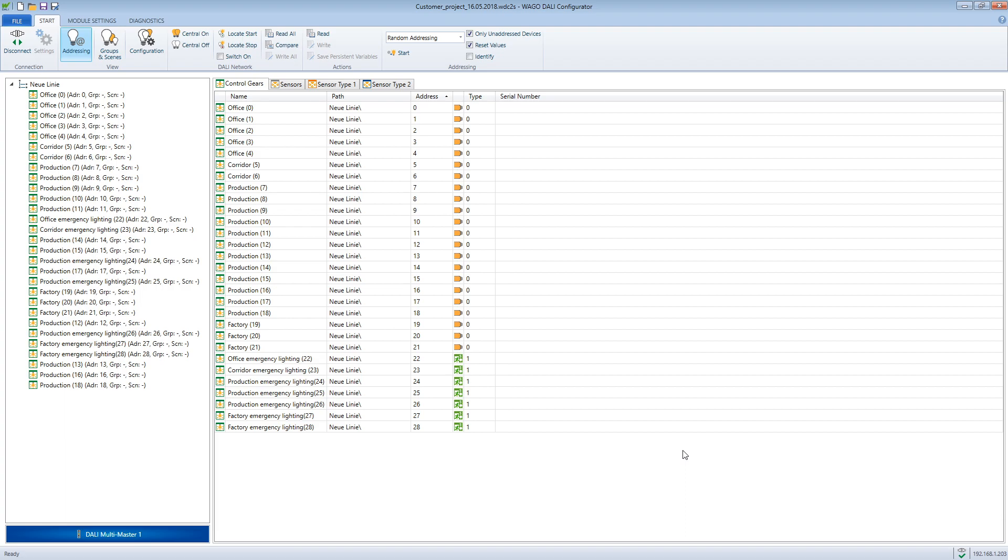Now we come to the extension. The new equipment can now be installed and connected to the DALI bus. In doing so, the installation conditions with regard to cable lengths, cable cross sections and the maximum number of control gear must be observed.